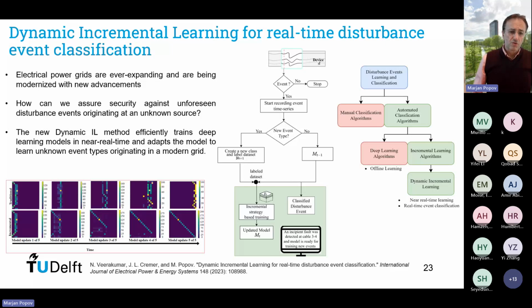Normally, it is not only important to detect faults. Once we detect a fault, protection will operate. However, we need to detect the sick operation of the power system. This could be, for instance, a lot of harmonics due to interaction of different components, or aging of the equipment that may cause arcing, or it could be something else, lightning for instance, or other disturbances that are not so critical as to immediately cause failure of the power system. However, they will accelerate the system aging or cause sudden system failure.